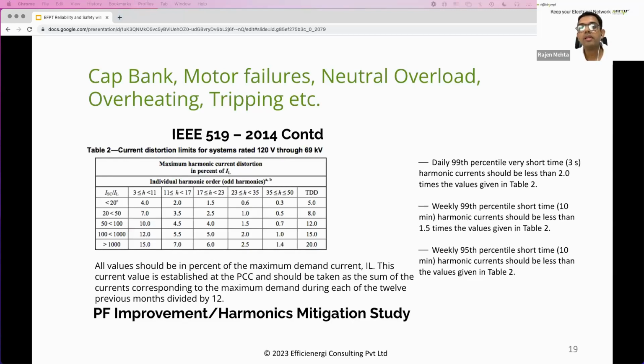Going further—impact of PQ and PF on reliability of electric equipment, challenges. Which is the best instrument to measure harmonics? I wouldn't say 'best,' but as per the standards, IEC 61000-4-30 Class A Edition 3 compliant instruments are the ones which should be used for measuring harmonics in your facility, so there's no ambiguity or dispute when sharing that data, whether for compliance purposes or for harmonic filter sizing.